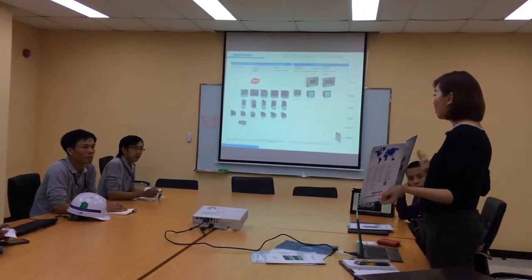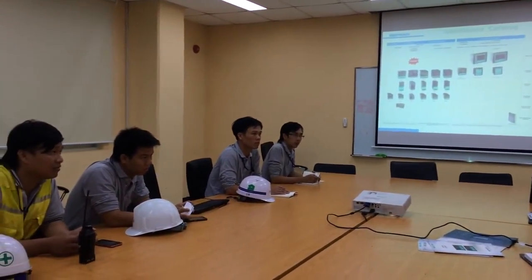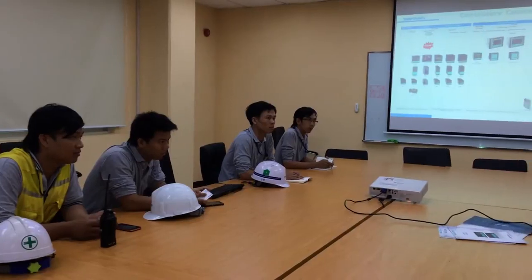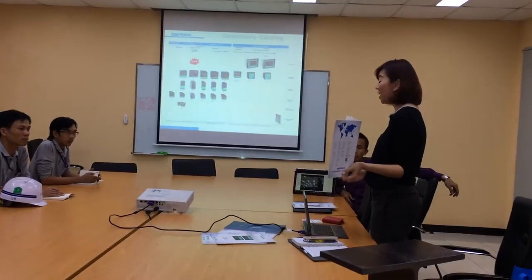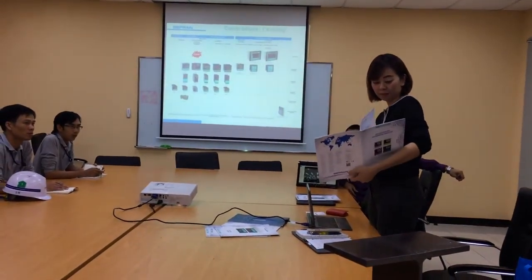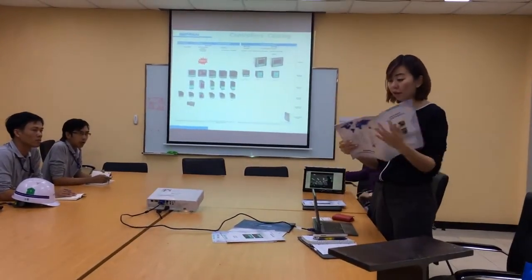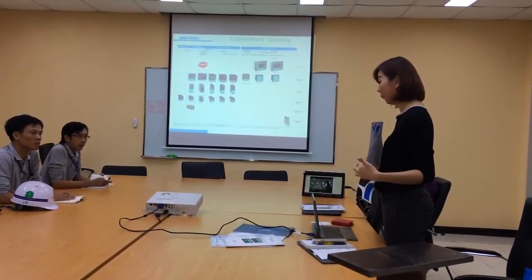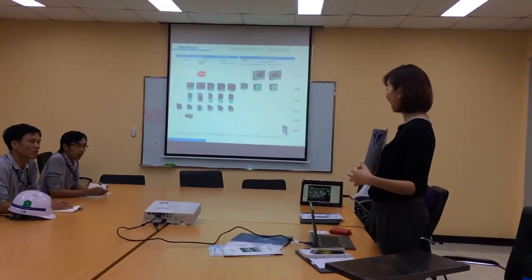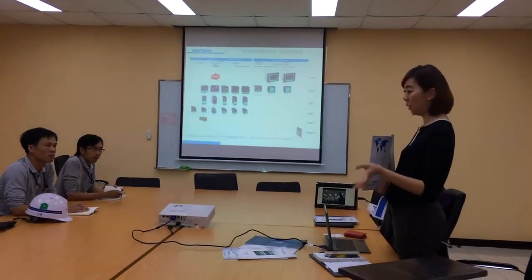Normally for your machine, if you need to count the energy, you need to get a separate controller with the CT, correct? But this comes with the function inside the controller as an optional function. So if you want the energy counter function, you just add that option. It also comes with logic control programming. The logic block program has a 12-step logic program, so it works like a mini PLC as well. All this comes as an option. You can choose to have it or not.